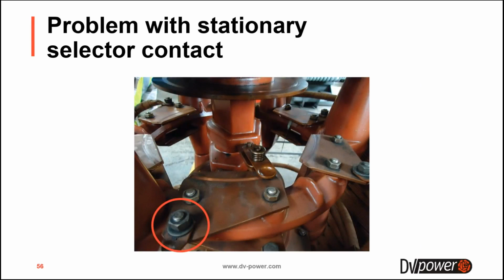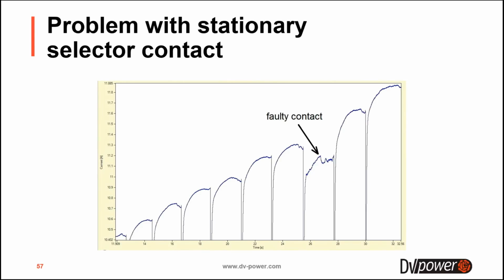After that, we returned the spring of the moving contact to the proper state, and we simulated a problem with the stationary selector contact, which is represented here with the red circle. So we loosened this bolt on the stationary contact, and we can see that every transition is a good one, except this one, where it is obvious that we have a faulty contact, that we have increased resistance, which caused a higher drop of current even before the transition starts.